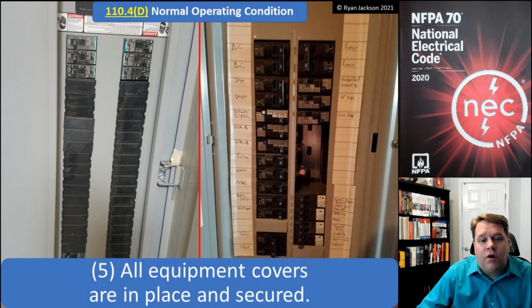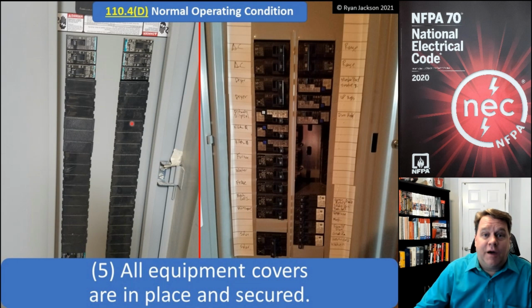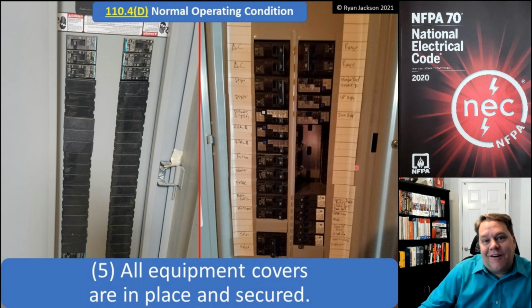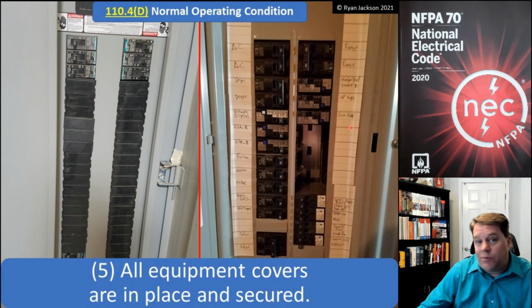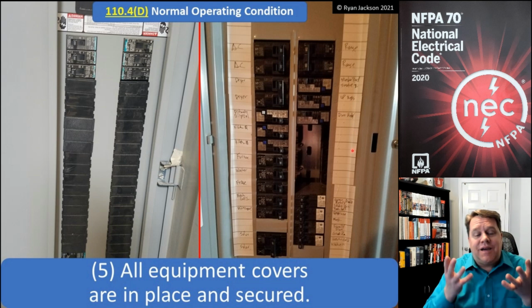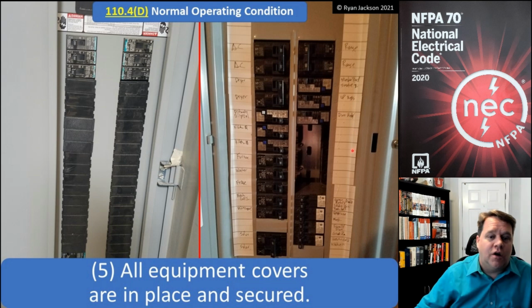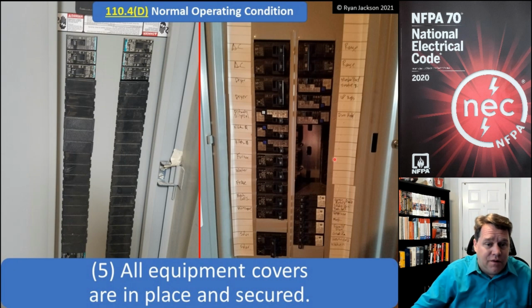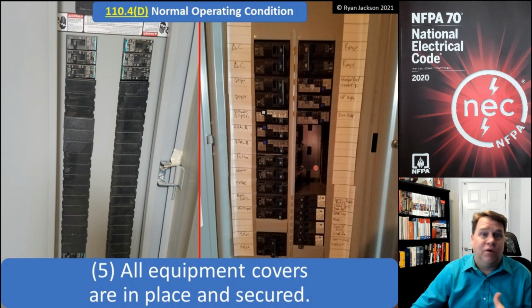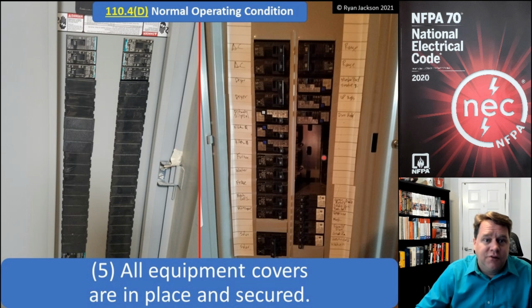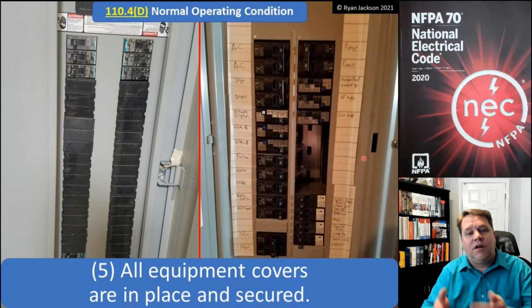What about the panel board on the right? Well, we're missing some of the panel blanks because we had to use them on the other panel. So is there any normal operation of these circuit breakers? No, I can't walk up and start turning these breakers on and off because I have no idea what kind of dirt or flammable materials or critters, mice and insects. Well, I don't know what's inside of that panel. So there is no normal operation of that equipment because it's not in a normal operating condition.